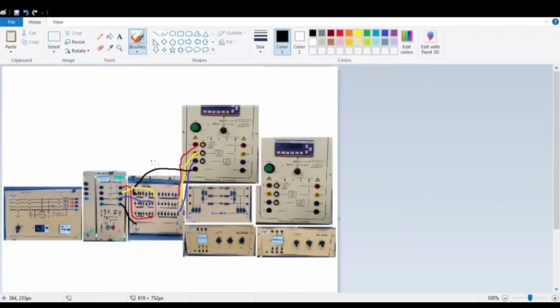Also the neutral wire is connected from the circuit breaker to the 3-phase transformer, and connect it again within the circuit breaker, red, yellow and blue like usual.